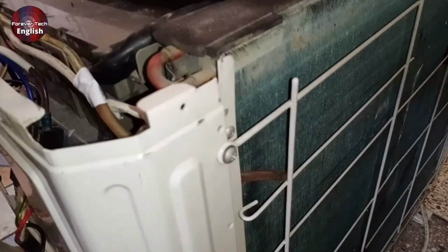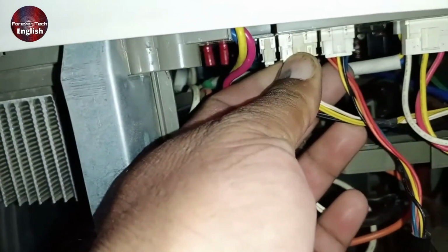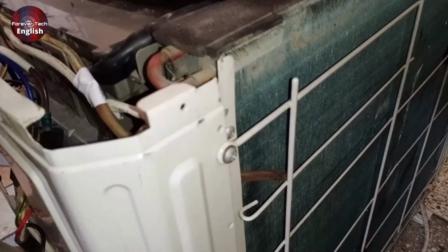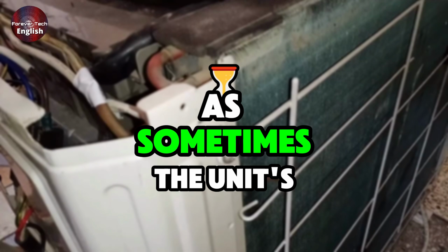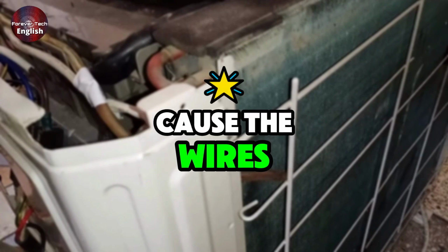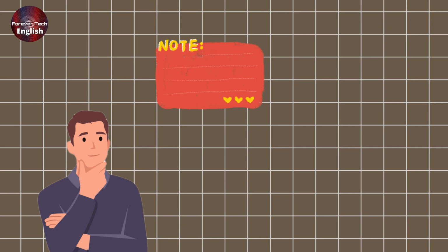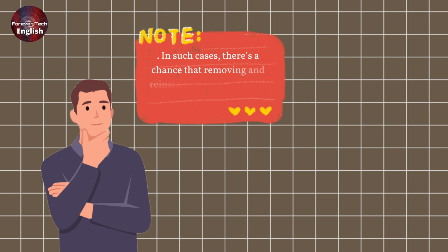Now, I will explain how to fix it. First, check the connector to ensure there's no loose connection. Check the cable to see if it's broken or cut anywhere. Also, try removing the connector and reinstalling it, as sometimes the unit's vibrations cause the wires and connectors to become loose. In such cases, there's a chance that removing and reinstalling it might fix the issue.